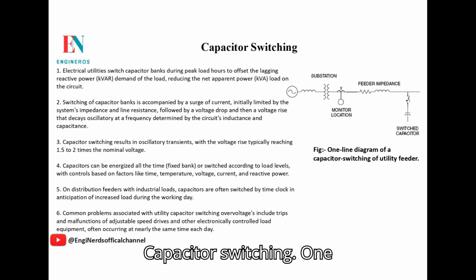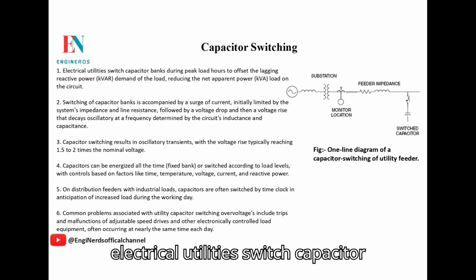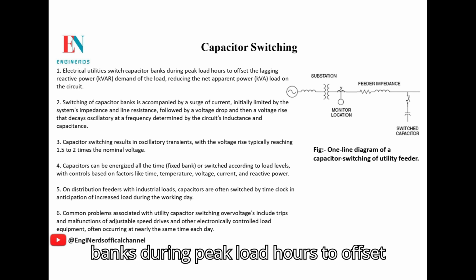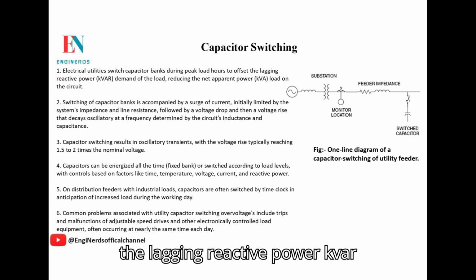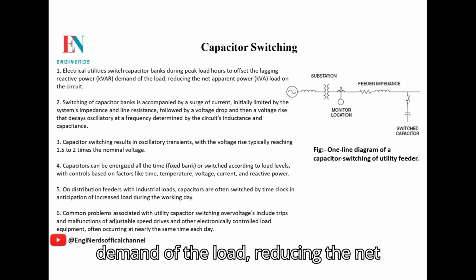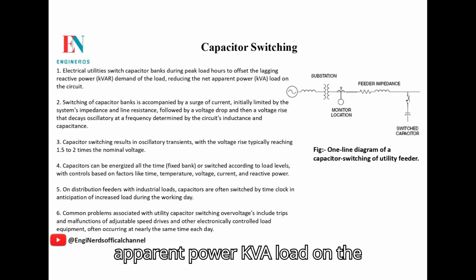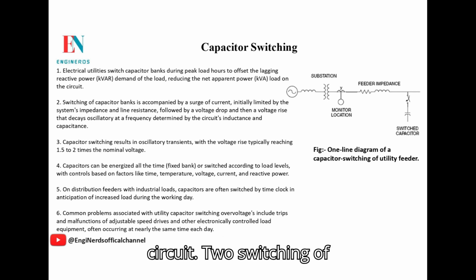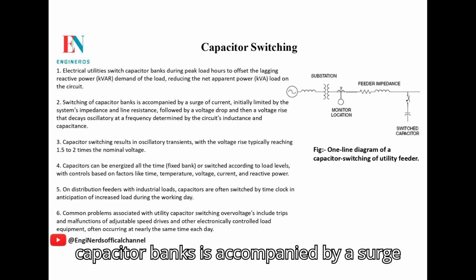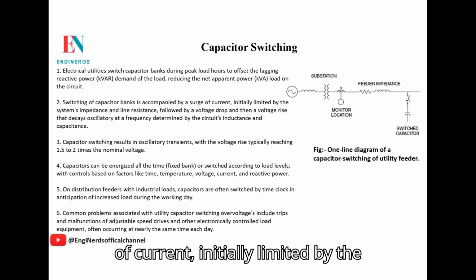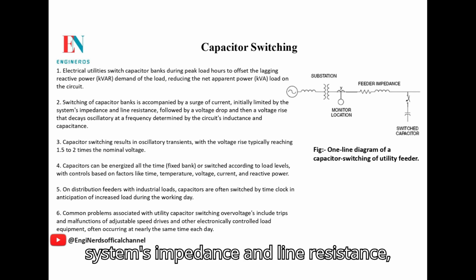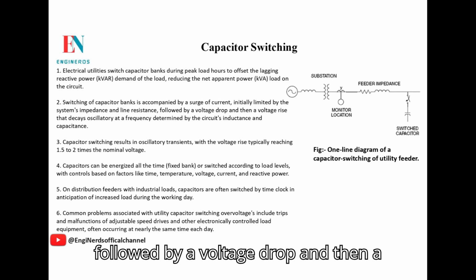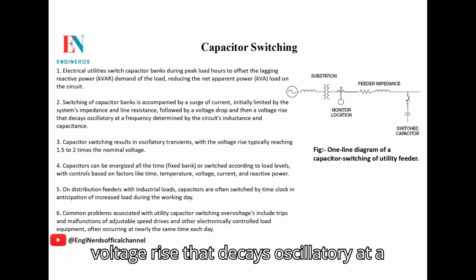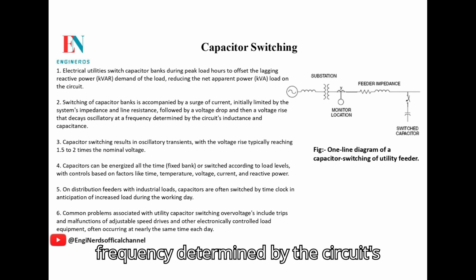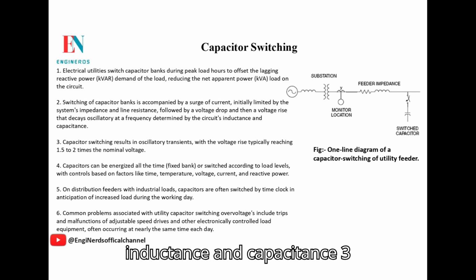Capacitor switching. 1. Electrical utilities switch capacitor banks during peak load hours to offset the lagging reactive power, kVAR, demand of the load, reducing the net apparent power, kVA, load on the circuit. 2. Switching of capacitor banks is accompanied by a surge of current, initially limited by the system's impedance and line resistance, followed by a voltage drop and then a voltage rise that decays oscillatorily at a frequency determined by the circuit's inductance and capacitance.